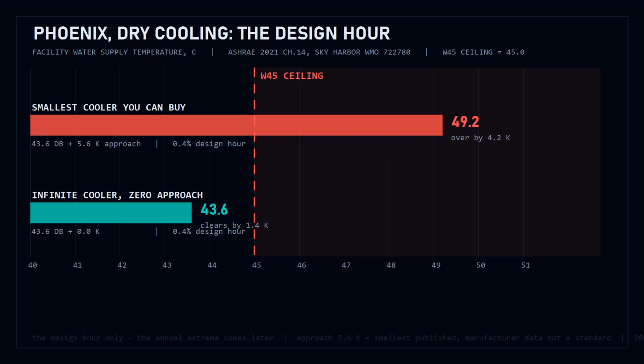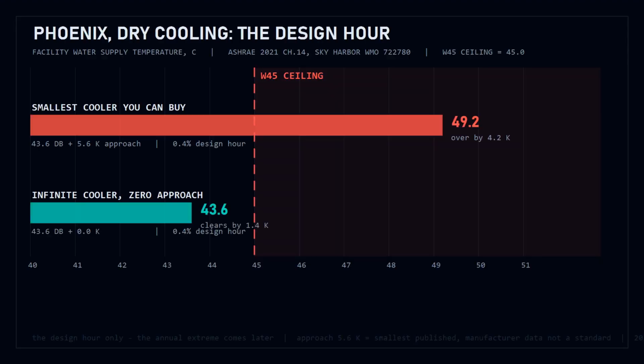So at the design hour, the physics permits it and the catalog does not. No dry cooler on sale lands anywhere in that gap. The smallest approach you can buy is 4 times the margin you have. That is a market wall, not a physical one. Except 43.6 is the 0.4% figure. It is exceeded about 35 hours a year.